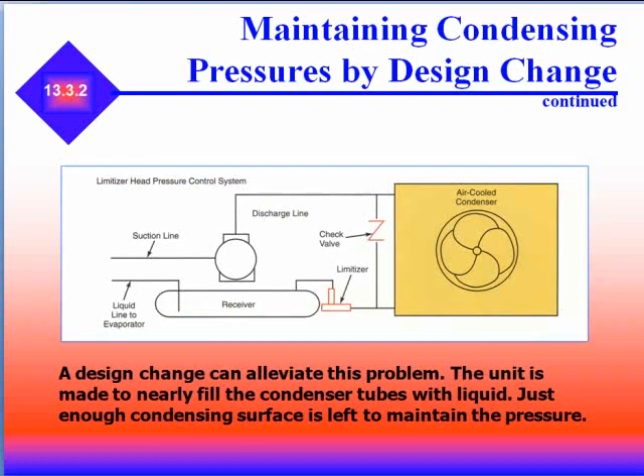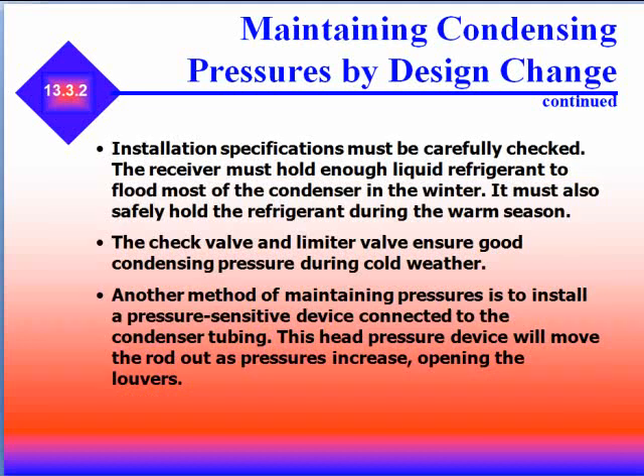A design change can alleviate this problem. The unit is made to nearly fill the condenser tubes with liquid — just enough condensing surface is left to maintain pressure. Installation specifications must be carefully checked prior to doing this. The receiver must hold enough liquid refrigerant to flood most of the condenser in the winter, and must safely hold the refrigerant during the warm season. Check valves and limiter valves ensure good condensing pressure during cold weather.